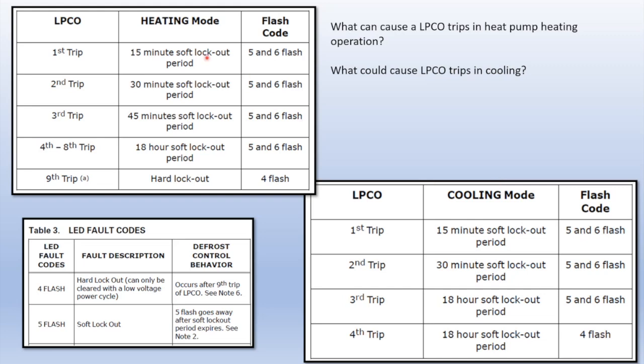So a first trip is going to be a 15-minute soft lockout, where you're going to see a 5 flash. Second trip, 30 minutes. Third trip, 45 minutes. Fourth to eighth is going to be 18 hours each. And once you hit 9 trips, you're going to have a hard lockout, which will give you 4 flashes. And LPCO is the only thing that can cause a hard lockout on our heat pumps.